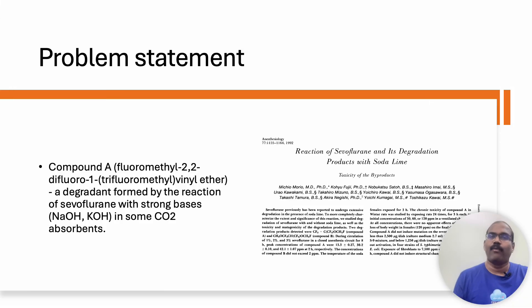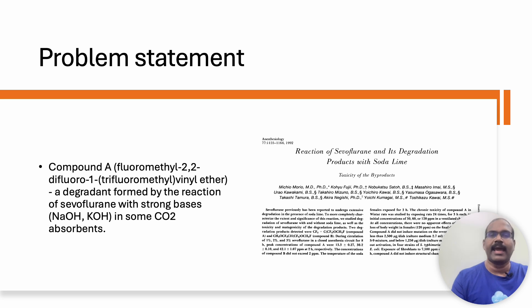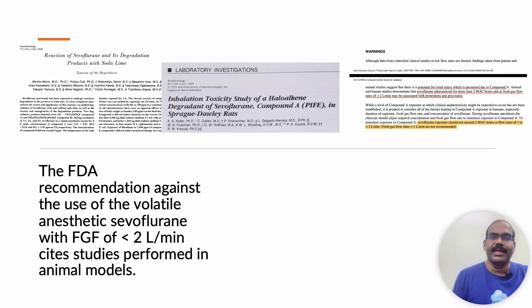First, let us check why there were concerns against the use of low fresh gas flows with sevoflurane. The manufacturer label for sevoflurane cites studies in animal models that showed evidence of renal toxicity due to exposure to Compound A — that is fluoromethyl-2,2-difluoro-1-trifluoromethyl-vinyl ether — a degradant formed by the reaction of sevoflurane with strong bases like sodium hydroxide and potassium hydroxide in some CO2 absorbents. The FDA recommendation is against the use of sevoflurane with fresh gas flows less than 2 liters per minute, citing studies performed in animal models.